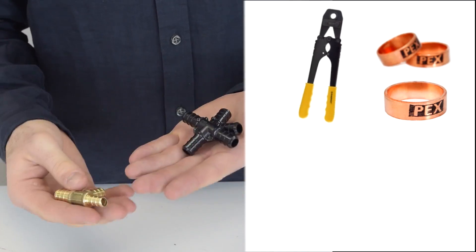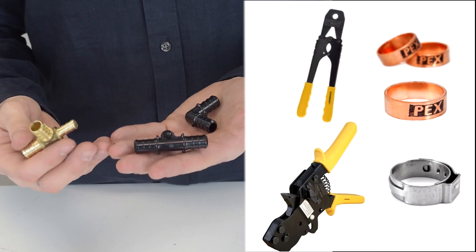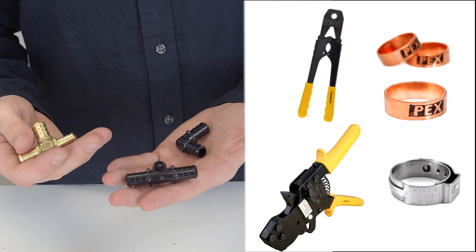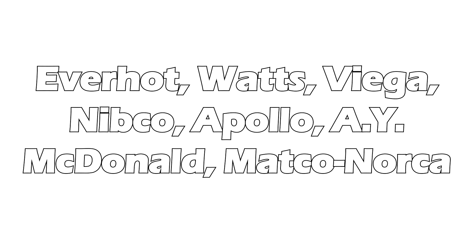It's available in brass or poly, and obviously you'll need a crimp tool and crimp rings for connection unless you're using the clamp method, then you'll need the cinch tool with cinch clamps. These are the biggest manufacturers of crimp and cinch fittings by brand. Crimping is compatible with all types of PEX tubing except for PEX-AL-PEX.